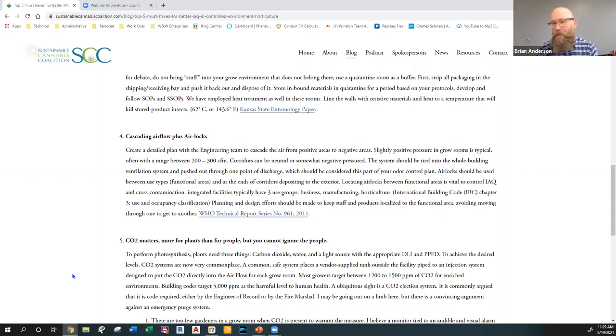But primarily, if you're changing air in a room six times, and the room has, let's say, 2,500 square feet at 10 feet tall, that's 25,000 cubic feet of air. Six times an hour means that air is moving fast in there. You know, these facilities are loud.